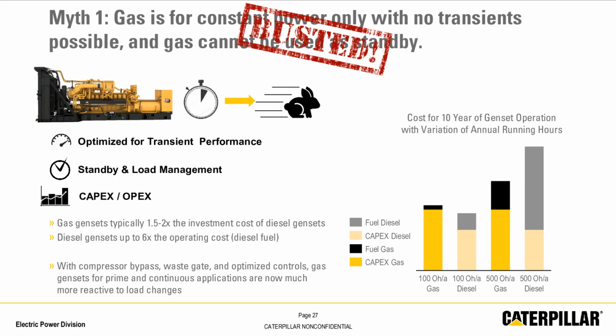Gas gensets usually have a higher investment for a genset that's ready to run, in some cases reaching up to 1.5 or 2 times the investment of a comparable diesel genset. But at the same time, the operating cost for diesel is significantly higher, up to 6 times the operating cost for gas gensets, primarily driven by the cost of diesel fuel compared to gas fuel.